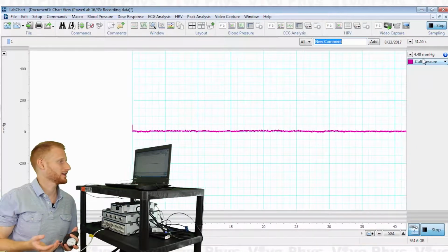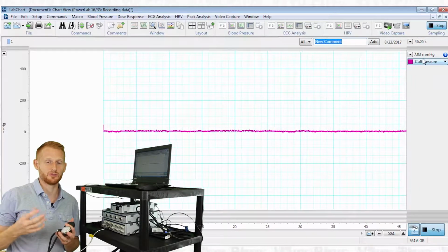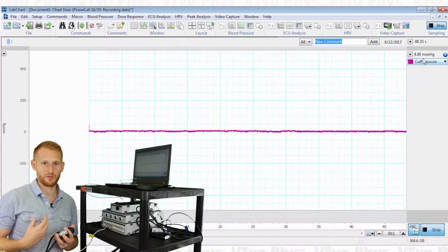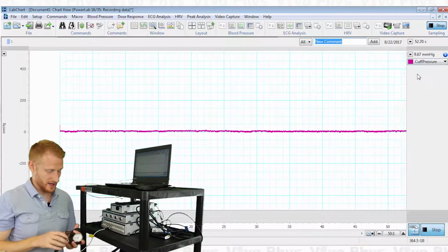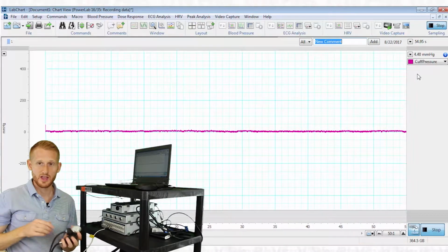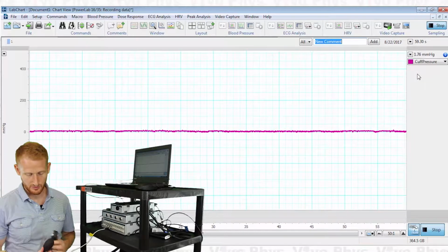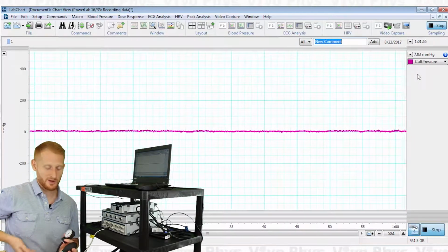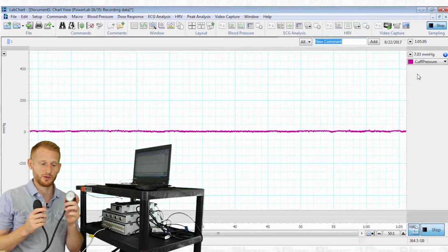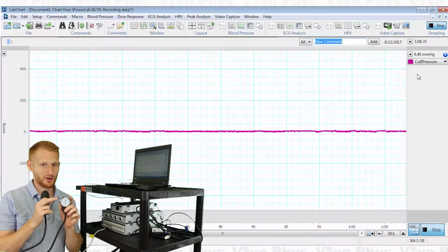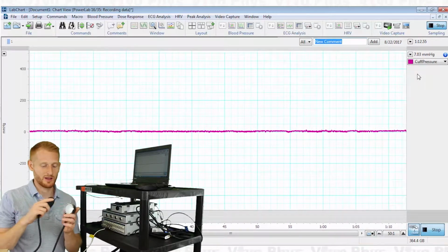All right, so for blood pressure, probably not the best demonstration. It's probably okay, but this is going to be primarily used as just a system for occluding blood flow, with my research at least. So if we take this and start to actually inflate the cuff, just like any other manual cuff you've ever seen, it's going to have a little sphygmomanometer aneroid dial, which is going to show the actual pressure inside this. So you can always calibrate this pretty easily with a two-step calibration.